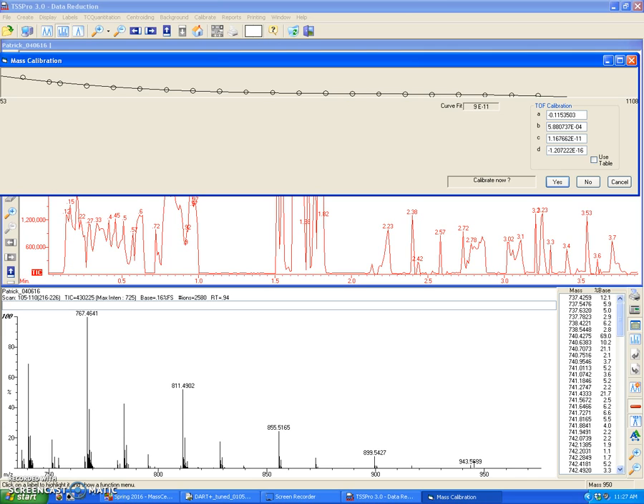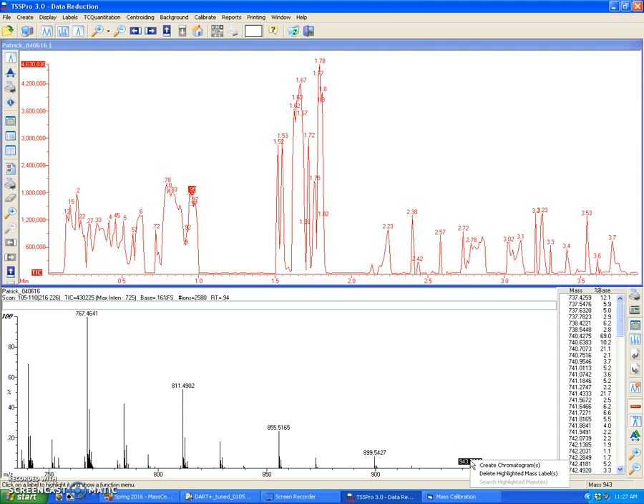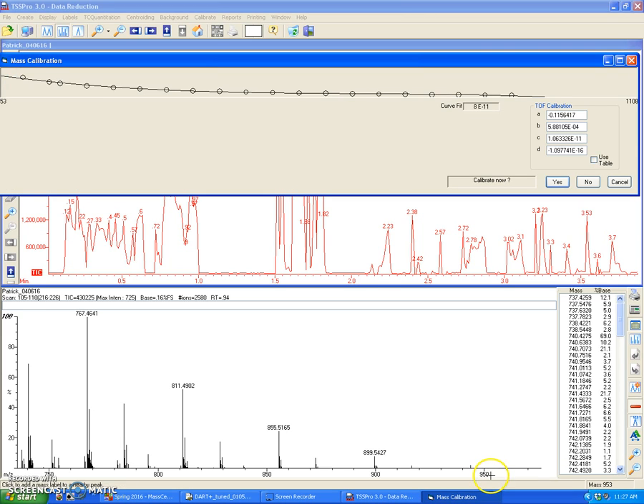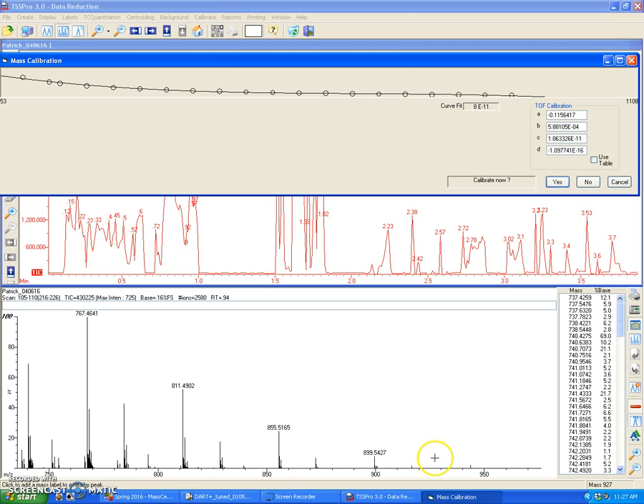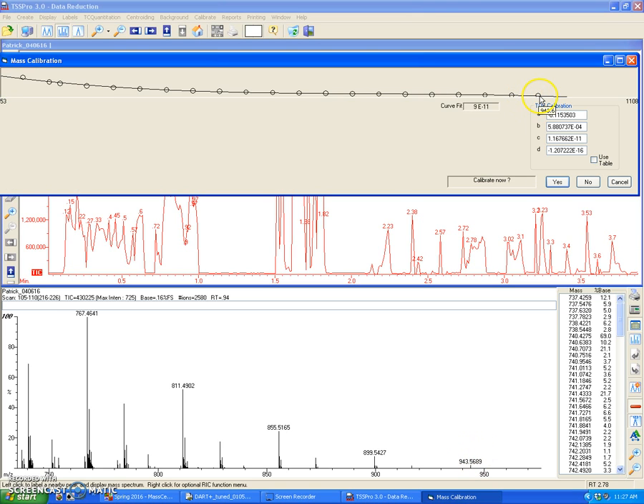So to delete this, all I have to do is click on this mass, so make sure that there's the arrow, left click, and click on delete highlighted mass label. And it actually dropped down the curve fit, so I'm going to put that back in by hovering over this mass spectral peak again and clicking, and that would input this as this point right here. So 9e to the minus 11 is very, very good, and I can accept that as my calibration by clicking yes.